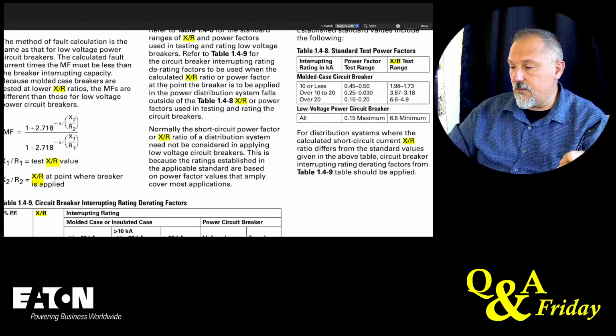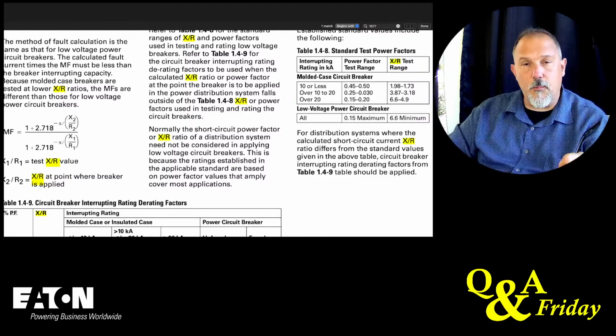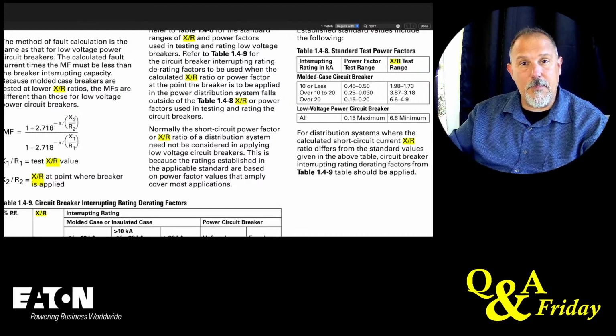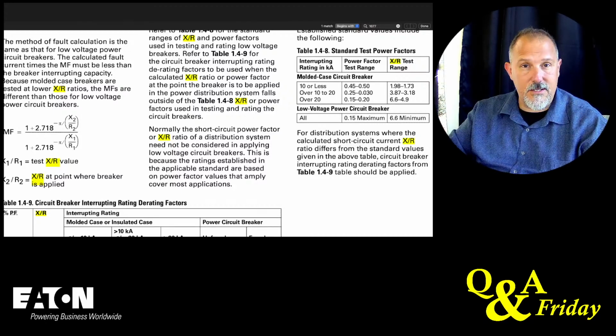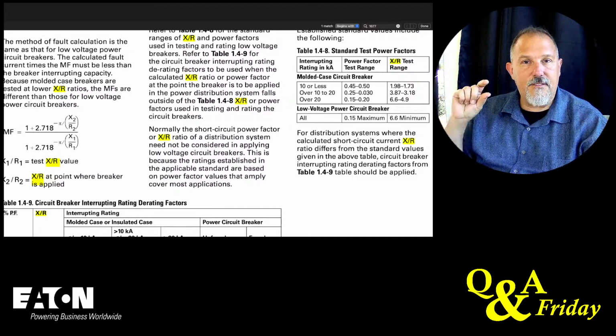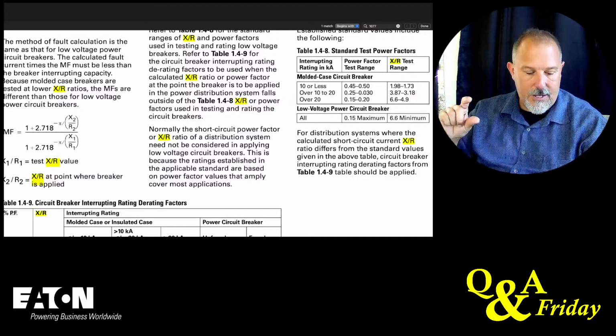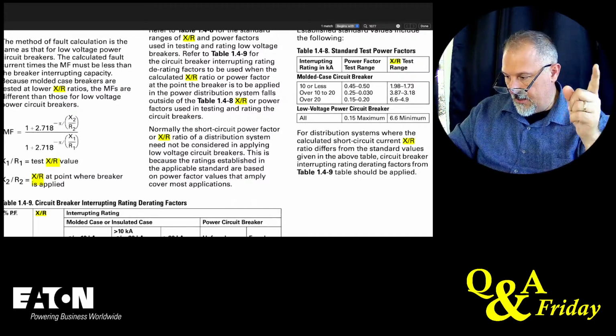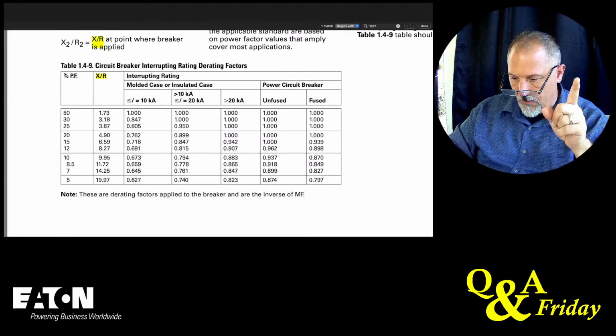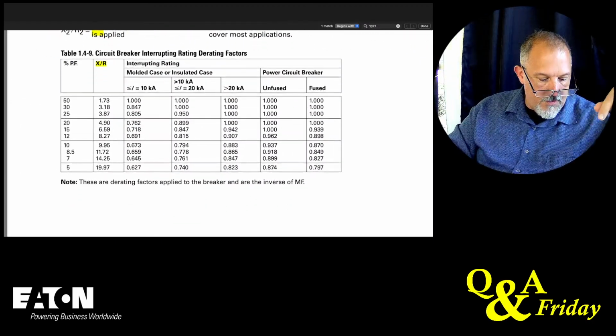The X to R test range for 10 amps or less is 1.98 to 1.73. Over 10 to 20 is 3.87 to 3.18. And then over 20 kA molded case circuit breakers, 6.6 to 4.9. So if you have a greater than 6.6 X to R ratio, you need to adjust the interrupting rating capabilities. It's not about the number of zero crossings. It's about that first half cycle. Okay, so that's the stuff I wanted to make sure I covered for that question.